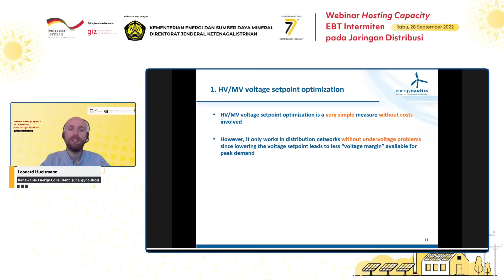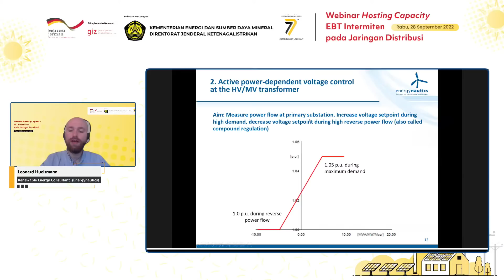You can then have more advanced voltage controls at the primary substation transformer. This is called compound regulation. I don't want to explain this in too much detail, but basically, during times of peak demand you may put a high voltage set point, and when you register a lot of reverse power flows because of distributed PV generation, you might, only in these situations, lower the voltage set point at the primary substation transformer. This can be a more efficient measure, but also a bit more sophisticated.